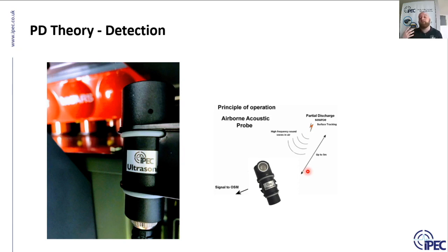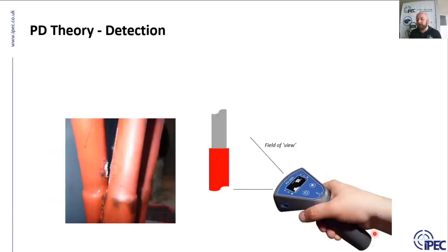What we tend to do now with permanent installations is we'll install the sensors inside the cable termination. So it's quite common for us now to take a shutdown, install the sensor very safely, and run a connector outside so that in future you can use portable equipment to test or connect it to a permanent monitoring system as well. Here's another animation. Ultrasonic sensors are very directional, it must be noted. They generally have a field of view of about 30 degrees, and so they're good for about 2 or 3 meters. The nice thing about ultrasonic is your location is conducted at the same time as your testing, if you like. As you swing the device around, you're pinpointing the location as well.